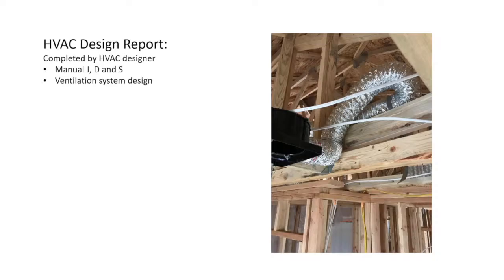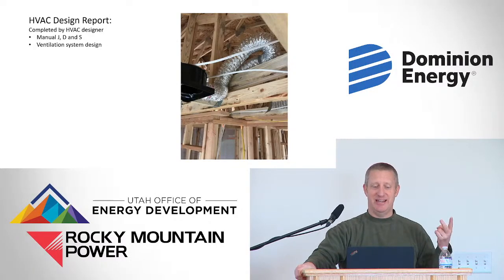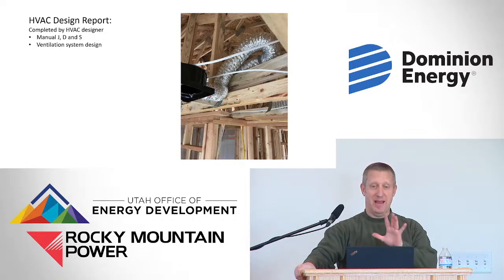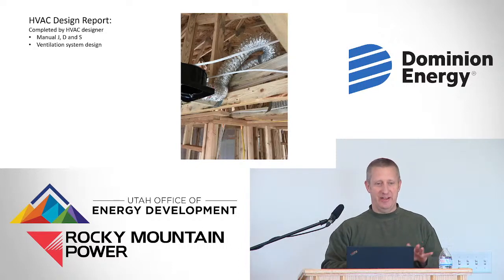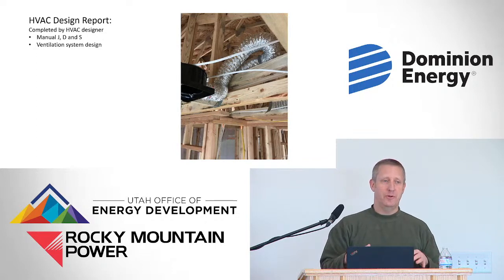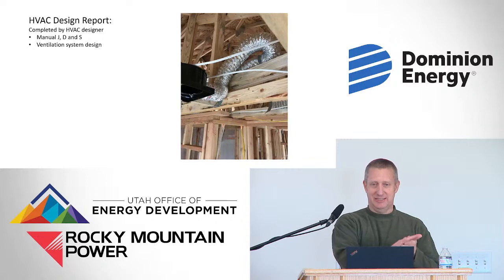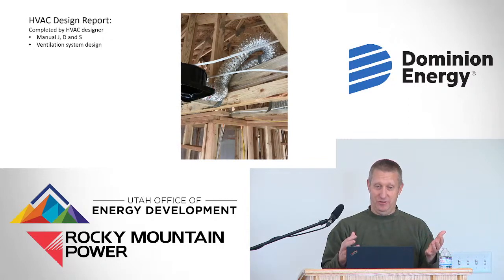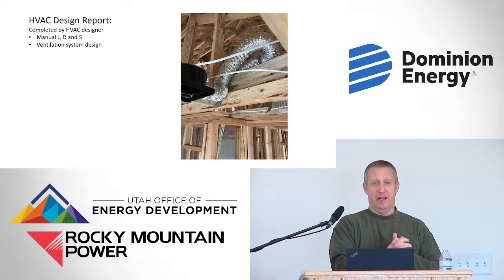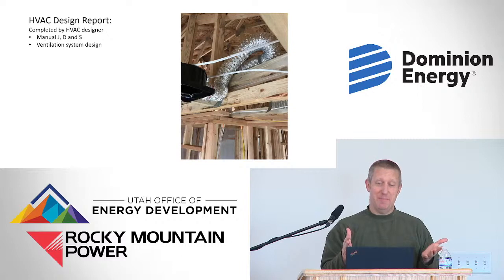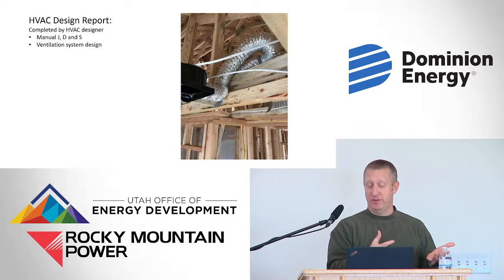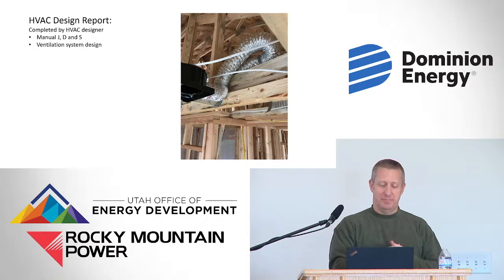So there are design programs. Manual J does the sizing, Manual D is the duct design, and Manual S is the equipment selection. Doing these three things, along with having the plans and specifications of the home, allows an HVAC contractor or engineer to design the system. Typically in residential new construction the duct system is assembled on site to fit the space allowed for it, and sometimes the home designer didn't do a good job of thinking about the HVAC system, so certain ducts end up smaller than they should be, which causes problems.